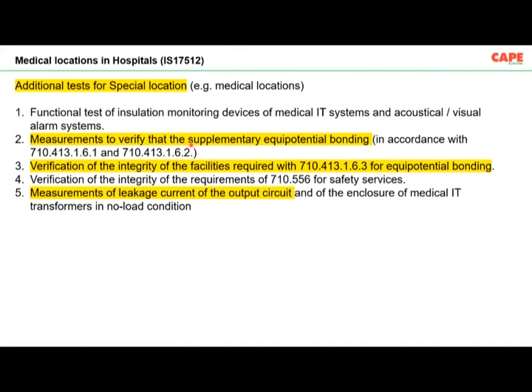Now the standard for the medical location says you are supposed to do the testing of the supplementary equipotential bonding. Now, verification of the integrity of facilities required for equipotential bonding. Every standard recommends making equipotential bonding. A good earthing means how good is your equipotential bonding. And the testings are also very much documented in all the standards. Now, let us say, for example, a hospital, how to do the testing of supplementary equipotential bonding. Unfortunately, only very few hospitals have made this protective measure. So there is nothing to test because the safety measure itself is missing in most of the places.